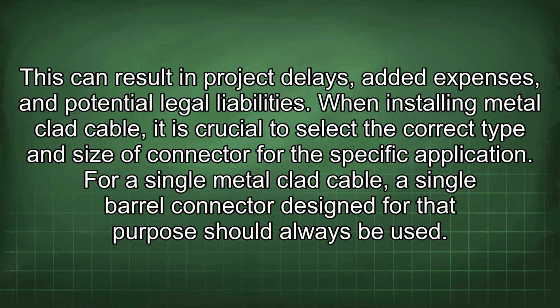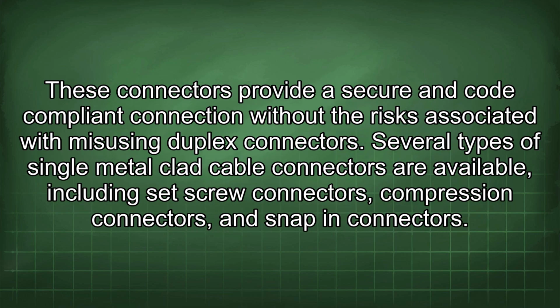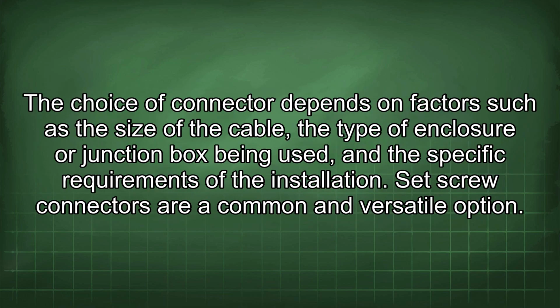When installing metal-clad cable, it is crucial to select the correct type and size of connector for the specific application. For a single metal-clad cable, a single barrel connector designed for that purpose should always be used. These connectors provide a secure and code-compliant connection without the risks associated with misusing duplex connectors. Several types of single metal-clad cable connectors are available, including set screw connectors, compression connectors, and snap-in connectors. The choice depends on factors such as the size of the cable, the type of enclosure or junction box being used, and the specific requirements of the installation.